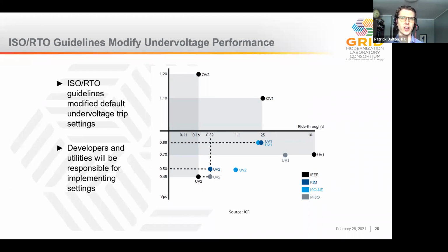We're currently working with New York ISO and the distribution utilities there on a similar type of decision point. This is a really important first key decision needed for IEEE 1547 implementation—how to strike that balance. It can be a longer discussion since people on the transmission side and distribution side come from different worlds, but we often recommend starting with the bulk system perspective quicker, to determine where these settings should fall for your particular region. It's also best to try to coordinate these responses over as wide a region as possible, and ISOs and RTOs, where there are organized markets, are a good mechanism for doing that.